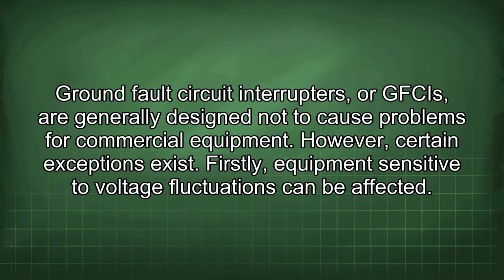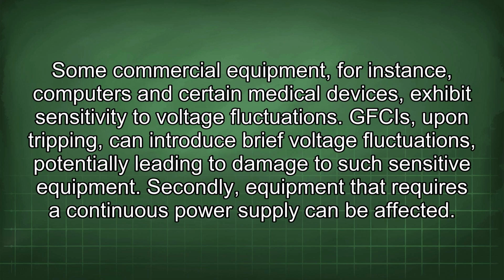Ground fault circuit interrupters, or GFCIs, are generally designed not to cause problems for commercial equipment. However, certain exceptions exist. Firstly, equipment sensitive to voltage fluctuations can be affected. Some commercial equipment, for instance, computers and certain medical devices, exhibit sensitivity to voltage fluctuations. GFCIs, upon tripping, can introduce brief voltage fluctuations, potentially leading to damage to such sensitive equipment.